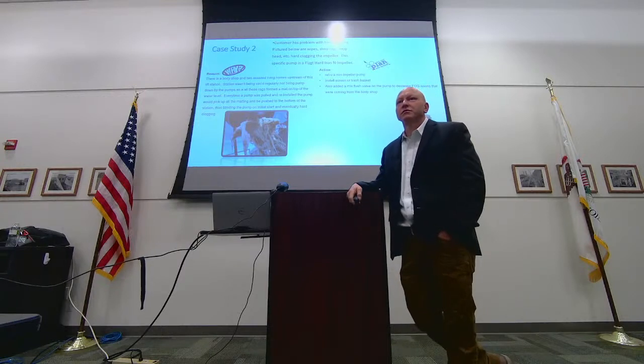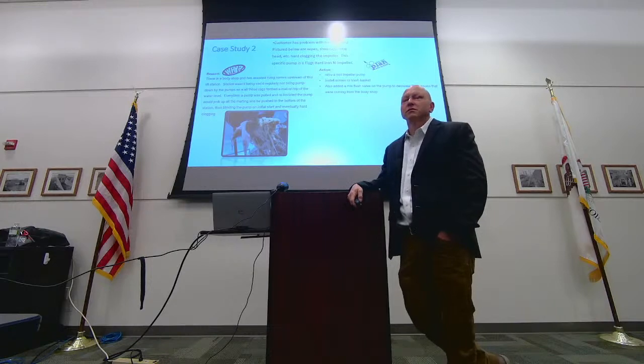So you're pulling that pump. I've got numerous pump stations, and it looks like they're pulling them out because of all the rags and everything else on them. Yeah. I've got Flygt, Simcoe, Gorman-Rupp. They all work. They all cut up stuff when they're in operation. It's when they stop and they can't restart. That stuff's all wrapped up in there. We're constantly backing out lift stations.